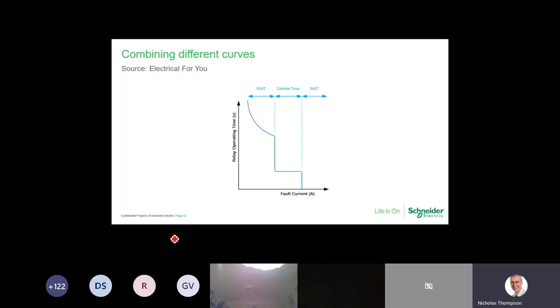So we've got 1 set point here, when I get my laser pointer. We've got a second set point here. So we've got 1 curve on the first set point, then a second curve on our second set point, and we've gone for instantaneous on our third set point. And these are the programmable characteristics you can put into a relay. And again, I'll reiterate, it is not for me to determine what the combination of curves is going to be. That will be done during a protection study.